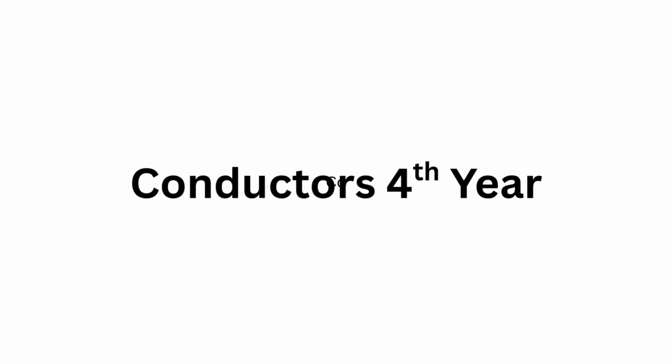Okay, so here's a final thought for you, the listener, to chew on. We know how critical managing heat is, both above ground and underground. We've seen the detailed rules for spacing and depth for those buried cables. So what kinds of unexpected, maybe long-term problems, particularly thermal issues that could force you to effectively lower the ampacity, might pop up if that required spacing or burial depth gets compromised during installation? Maybe the backfill isn't right or the conduit shifts slightly. How much does that real-world imperfection impact the theory the code is based on?